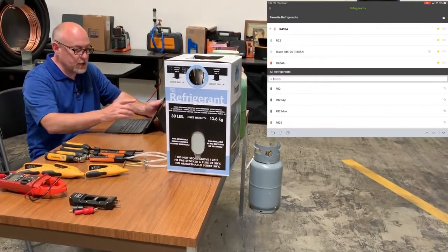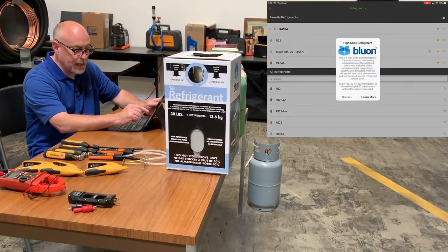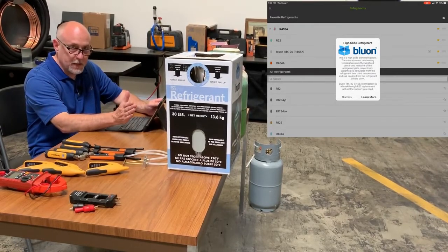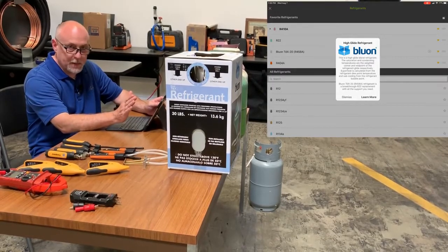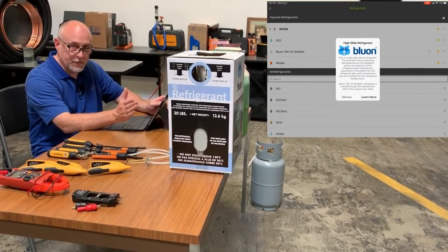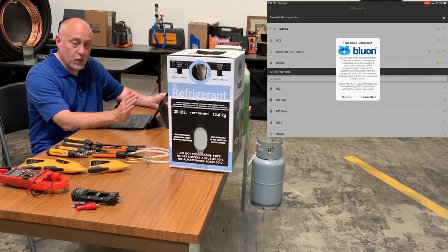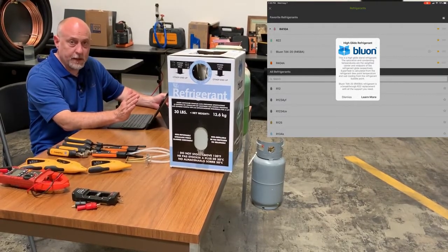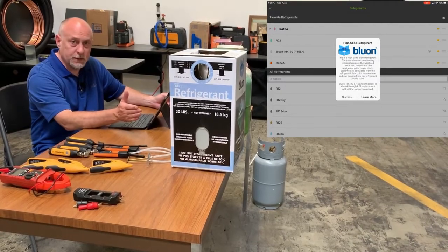Now one more thing here, on some of the refrigerants, we do have an I button. You'll see the I in there, and if you tap on that I, what it's telling you is some information about high glide refrigerants. Make sure you read that, because you'll notice sometimes in the Testo applications or the Fieldpiece applications, if you use those, that the superheat and subcooling are calculated a little bit differently, and we do that on purpose. Because in MeasureQuick, we're using midpoint and weighted midpoint to calculate the average temperature of the evaporator and condenser coil, and then we're using dew point and bubble point for superheat and subcooling respectively.